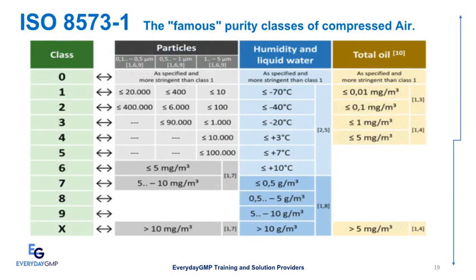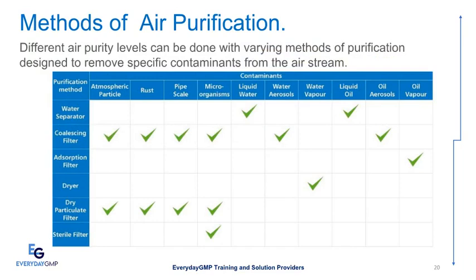ISO 8573-1 — the famous purity classes of compressed air. Here we see purity classes from 0 to X with reference to particles, humidity and liquid water, and total oil content. Different air purity levels can be achieved with varying methods of purification designed to remove specific contaminants from the air stream. Some methods used include water separators, coalescing filters, dryers, dry particulate filters, and, where required, sterile filters.